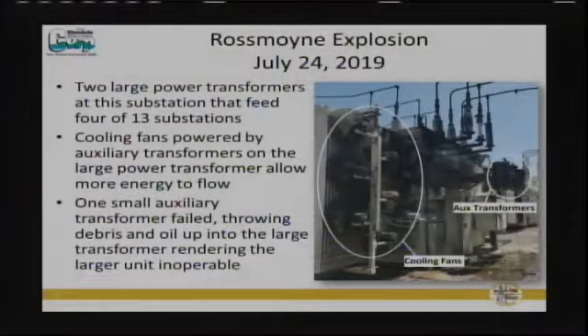The first event, or the main event, or the main incident, I should say, occurred at our Rossmoyne Substation, which on July 24th experienced an explosion of an auxiliary transformer. And if you look up on the right of that, you see that circled. Those are the auxiliary transformers, whose function is to provide power to the fans on the left, which are simply there to cool the main transformer.